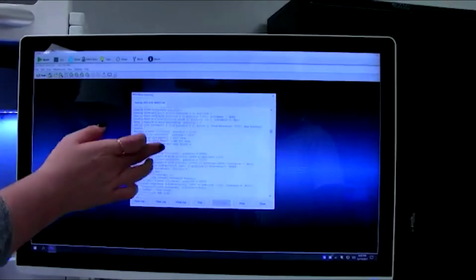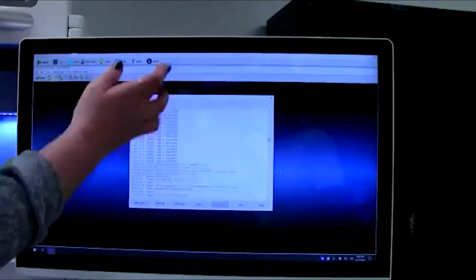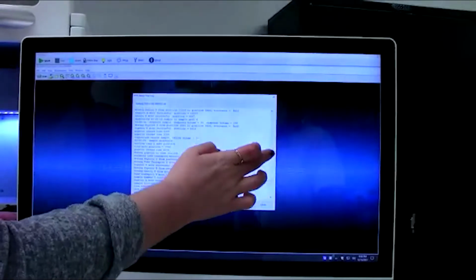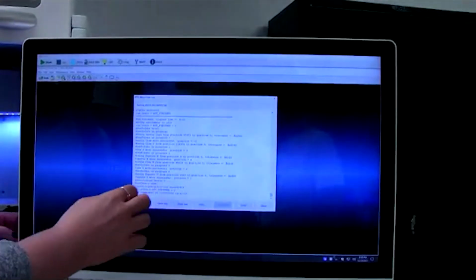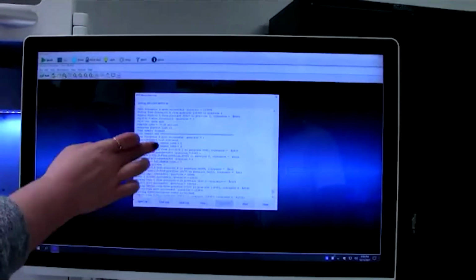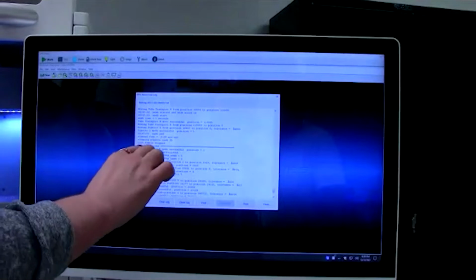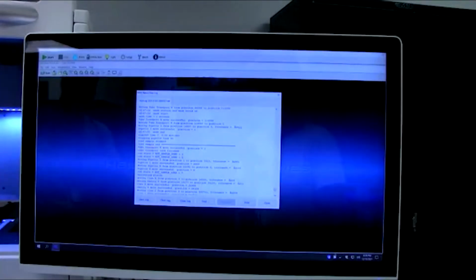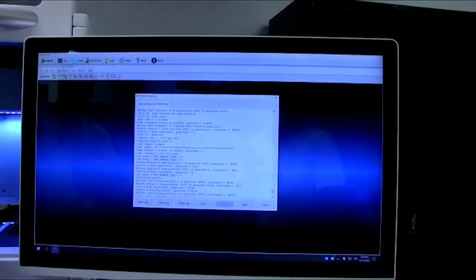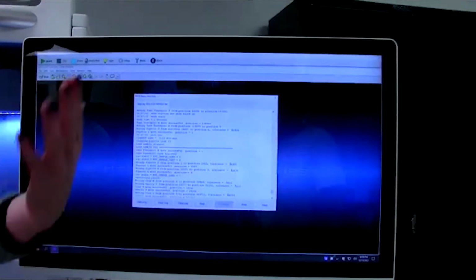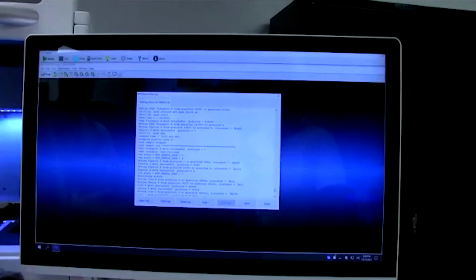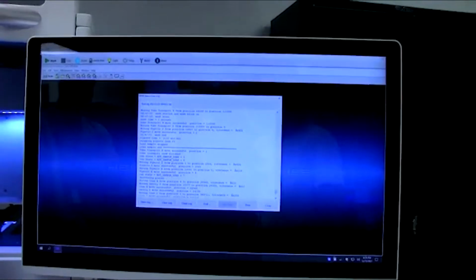And this is where you'll also want to come if you do have a blackout. When the power comes back on, you can go to the very end of the run log, and it will tell you the last process that began. So this is sample load end because we only did a sample load in that last run. But it might say destain, and you would know that the last process to run was destain and you were about to go into your dry step.